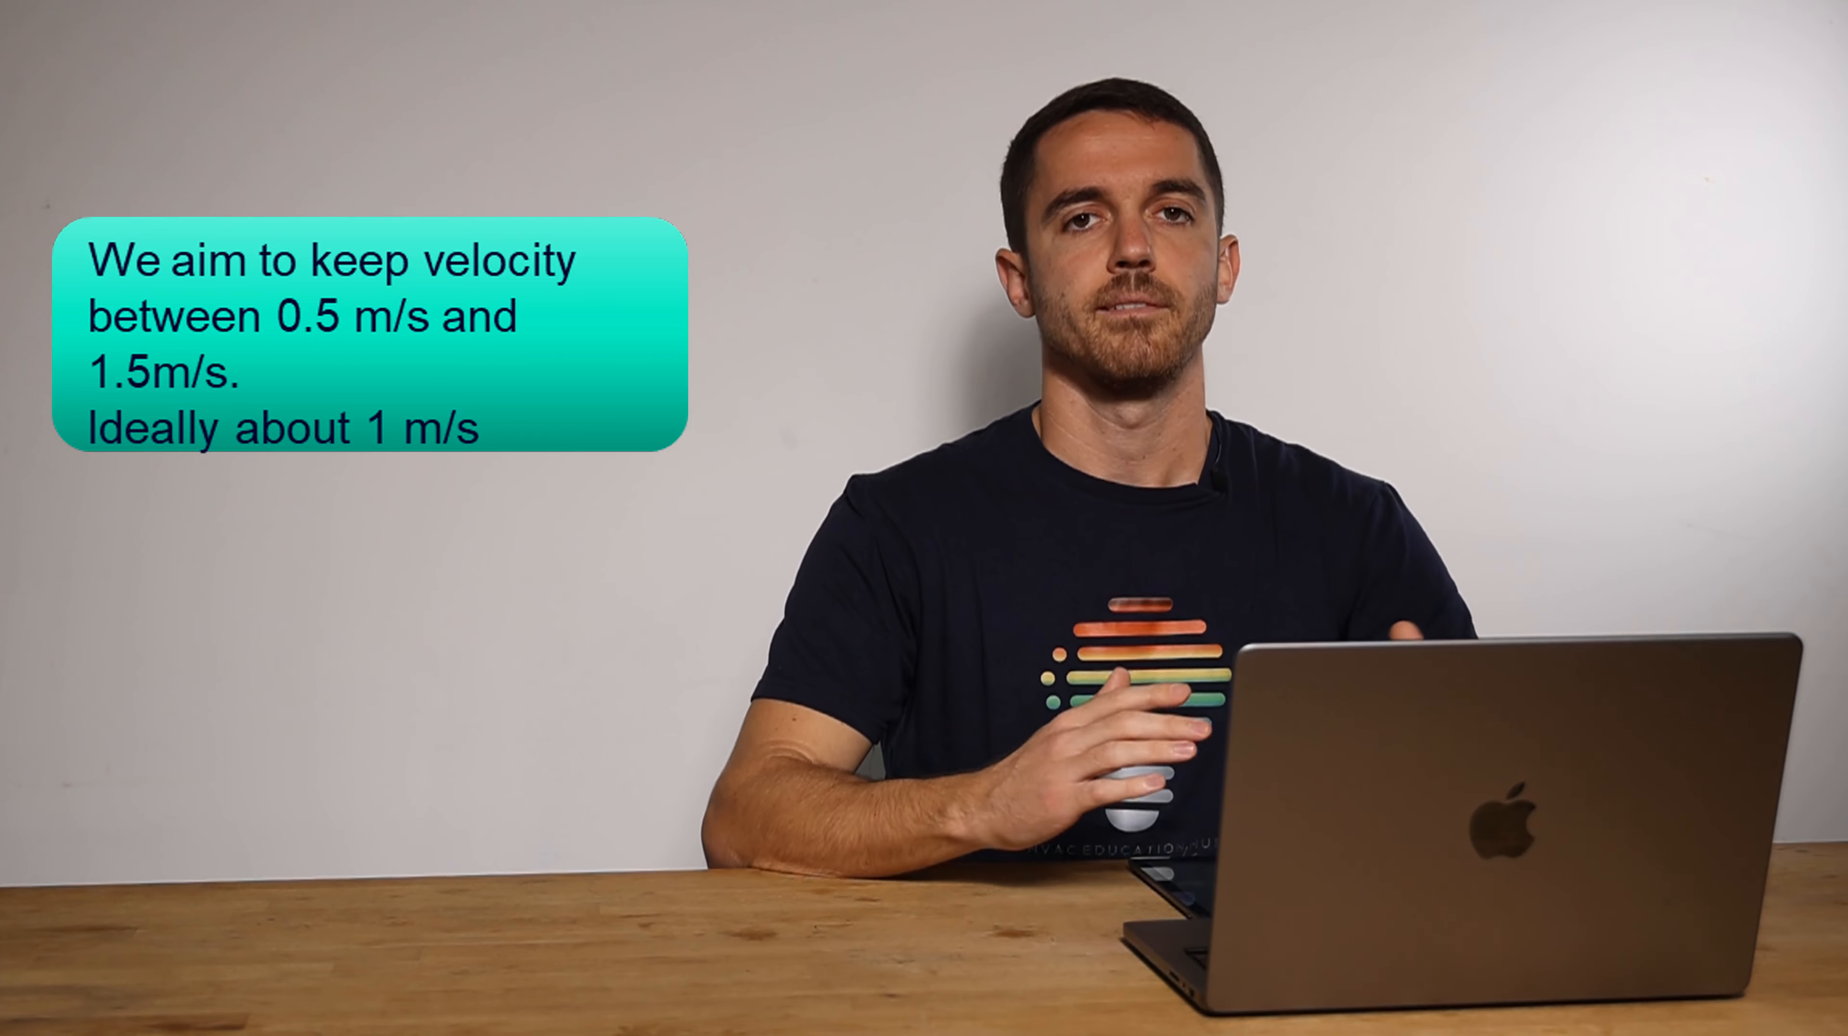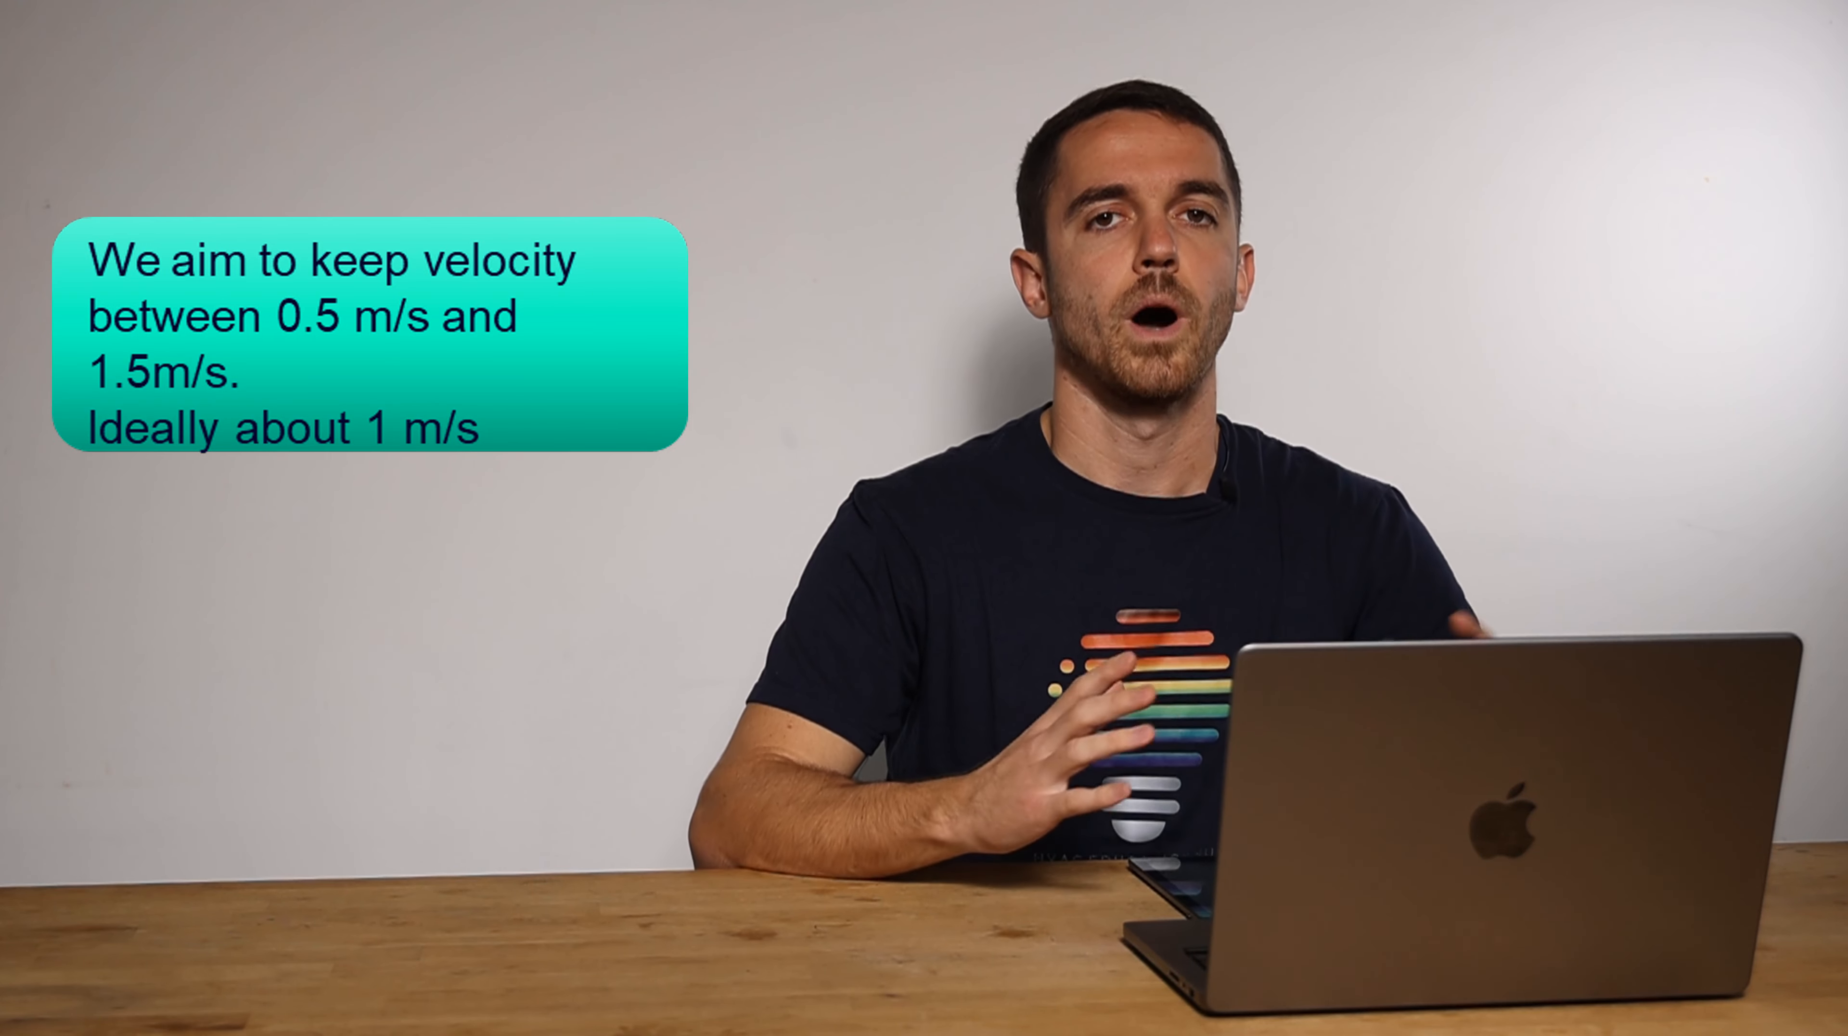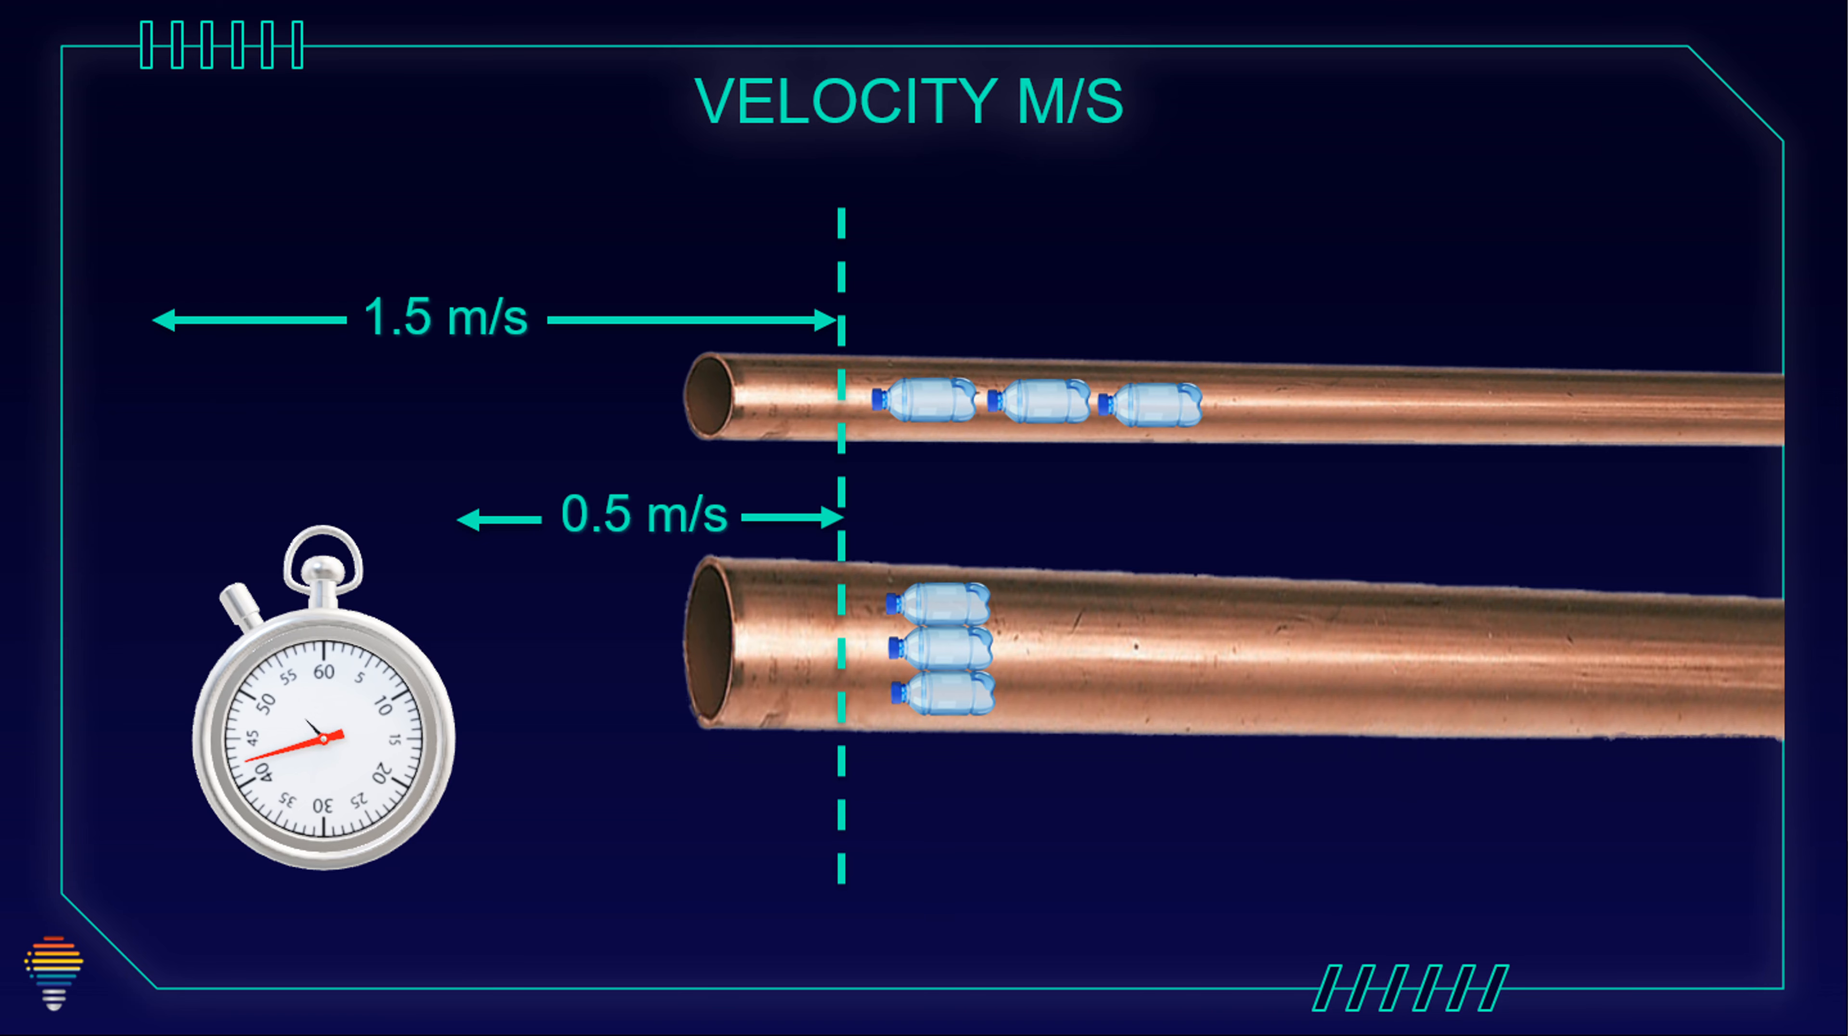Ideal is to have this velocity around one meter per second. If we have too small pipe, our velocity will be big and we will have noise in the system, big pressure drop, friction and we will spend more energy. However, if we have too big pipe, we will have some dirt in pipes because our velocity will be too small.